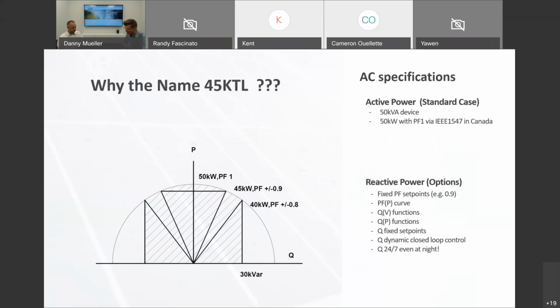So the most confusing part of the 45 KTL product from Huawei is actually the name, because the 45 KTL is a 50 kilowatt unit. And the reason why it's a 50 kilowatt unit is it's actually a 50 kVA unit. And in Canada, we are working on a fairly old grid code, the IEEE 1547, which still requires the inverter to operate at unity power factor, which means a power factor of 1. So for a 50 kVA device, you actually have 50 kilowatt active power available from that unit.